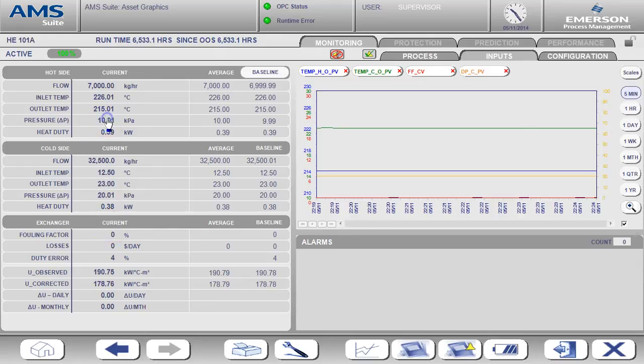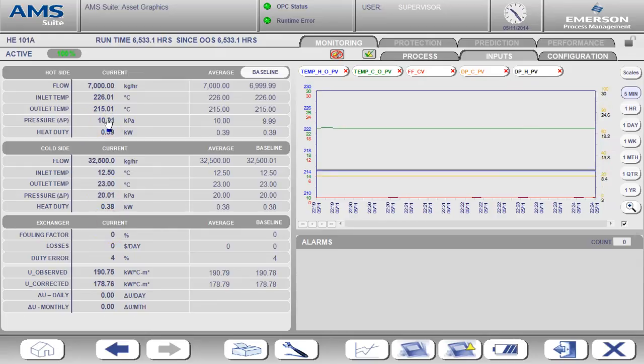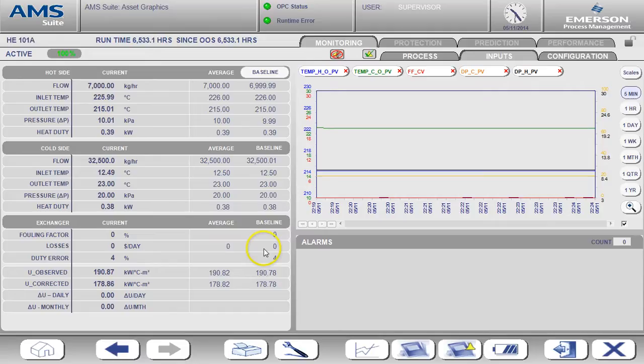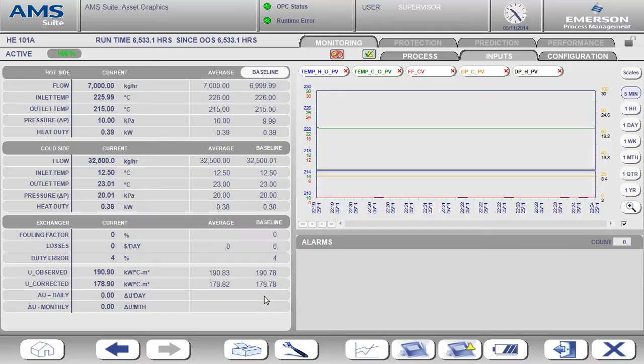The baseline values shown here represent a snapshot of the data that has been captured when the heat exchanger is clean. This creates the normal operating condition. Once the baseline is captured, all alerts are calculated as a deviation from this normal or clean operating condition.